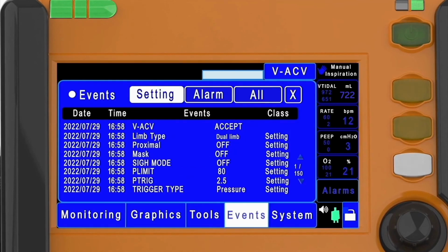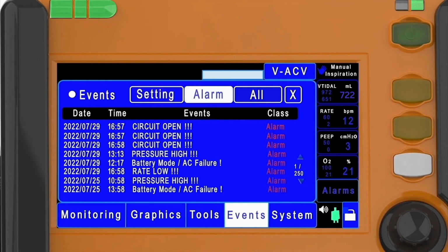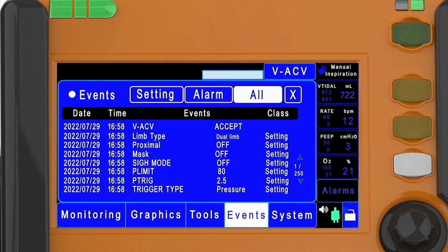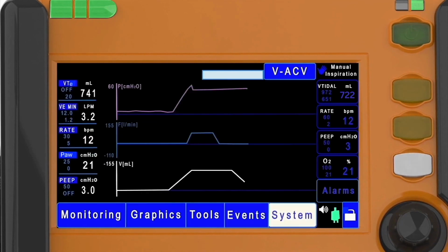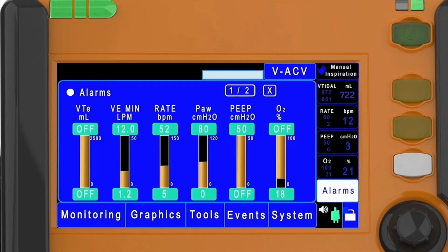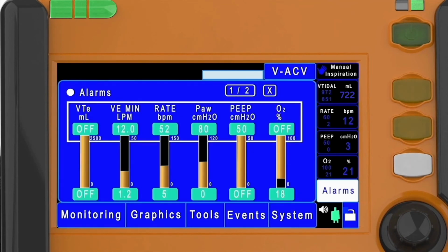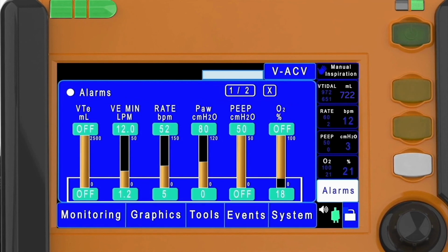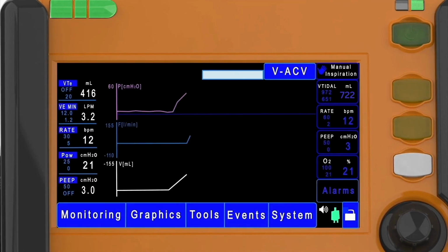Under the event section, you could observe different kinds of logs. You can also provide manual inspiration to the patient by clicking on the manual inspiration button on the top right side of the screen. The alarm section shows the upper and lower limits of the alarm parameters. To lock the screen, press and hold on to the lock symbol for 3 seconds. Do the same to unlock as well.